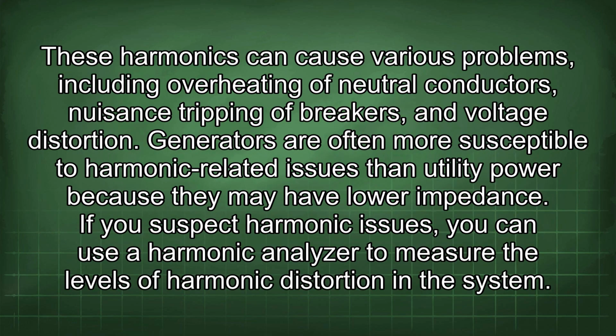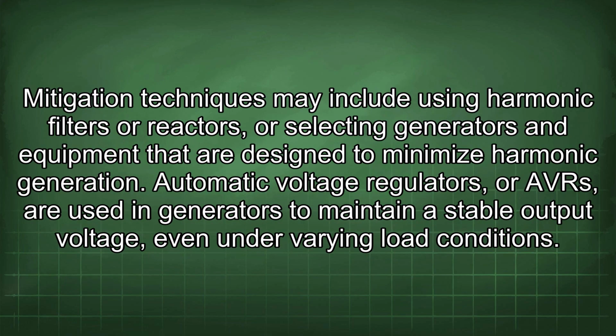These harmonics can cause various problems, including overheating of neutral conductors, nuisance tripping of breakers, and voltage distortion. Generators are often more susceptible to harmonic-related issues than utility power because they may have lower impedance. If you suspect harmonic issues, you can use a harmonic analyzer to measure the levels of harmonic distortion in the system.